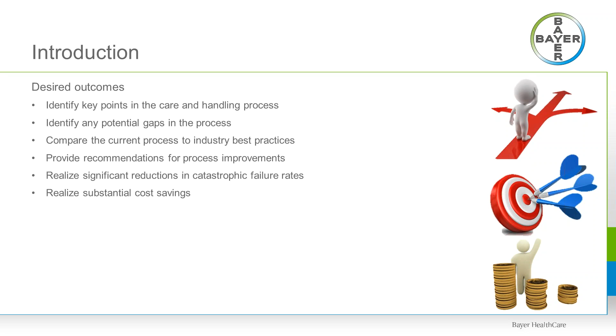If we list the most common modes of failure, they can really be divided into three categories with several overlaps. Obviously, we have the physical, the mechanical, as well as the electrical, and those overlaps are the electromechanical and the calibration failures and some damaged acoustical array. The highlighted modes of failure that I have here are what you can expect to encounter over the normal life cycle of a TEE probe given proper care and handling. Some of these failures, despite the best care and handling practices, will be ever present. Every electromechanical device ever created undergoes some level of wear, and almost every electromechanical device should undergo some level of preventive maintenance.